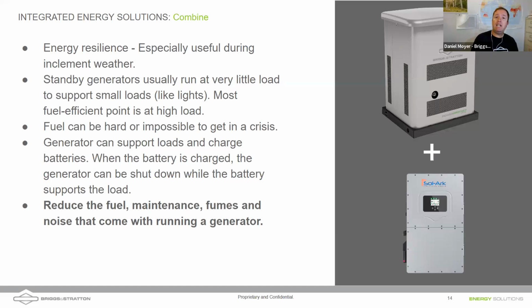But when we combine a generator and an energy storage system and we're off grid in a storm, we can add that extra level of energy resiliency. We can run the generator at a relatively high load. So we're going to run the generator hard, at its most fuel efficient point, and then shut that generator off. It saves fuel, which can be hard to get in a crisis. And as I mentioned, the generator is going to support the loads and charge the battery when it's running. You reduce the fuel.